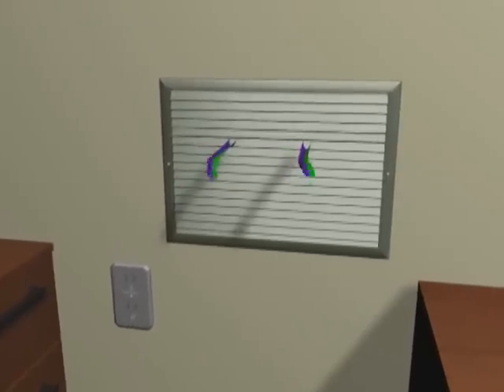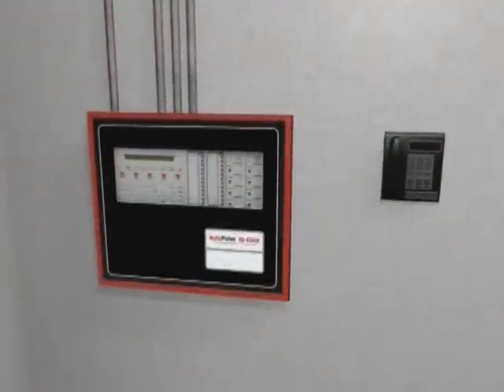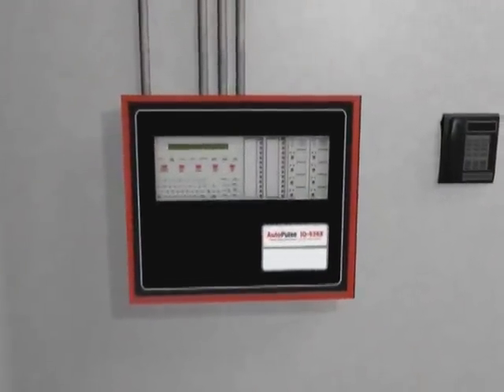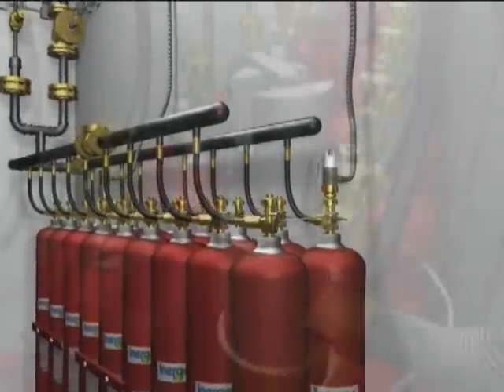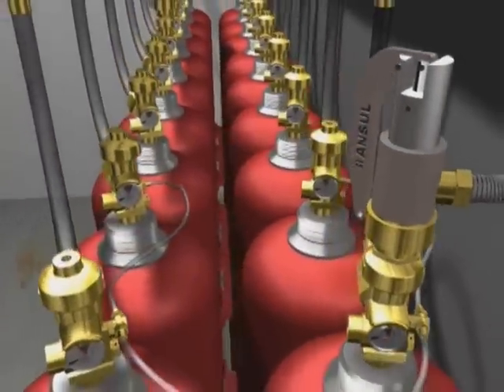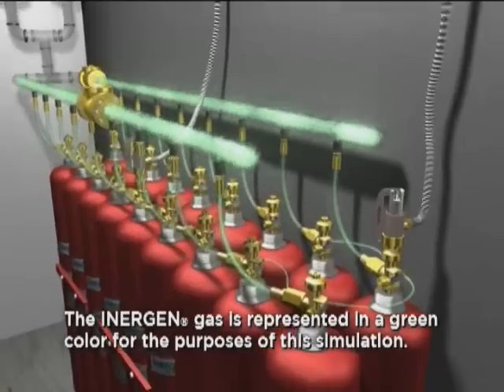The ventilation systems are closed off. After the prescribed time delayed period, the autopulse control unit energizes the electric actuator on the Inergen cylinder valve. The cylinder valve opens, allowing the Inergen agent to discharge from the storage cylinders.